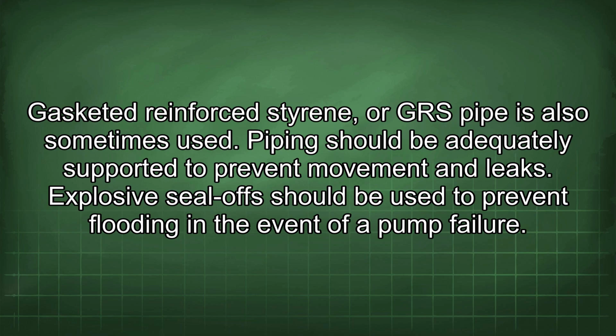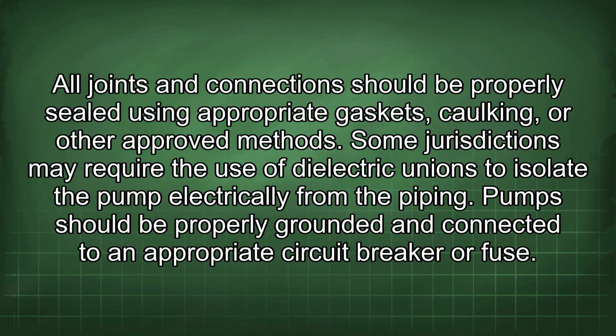Piping should be adequately supported to prevent movement and leaks. Explosive seal-off should be used to prevent flooding in the event of a pump failure. All joints and connections should be properly sealed using appropriate gaskets, caulking, or other approved methods. Some jurisdictions may require the use of dielectric unions to isolate the pump electrically from the piping.